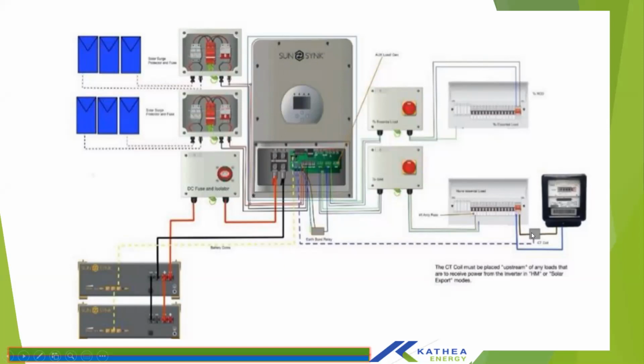And then your CT, you just need to wire. It comes with a cable with 10-meter length. As I said, make sure when you're extending, you use the same cable material as the one that comes with the CT. Usually, if you use different cable types, then the inverter won't be able to detect the CT.